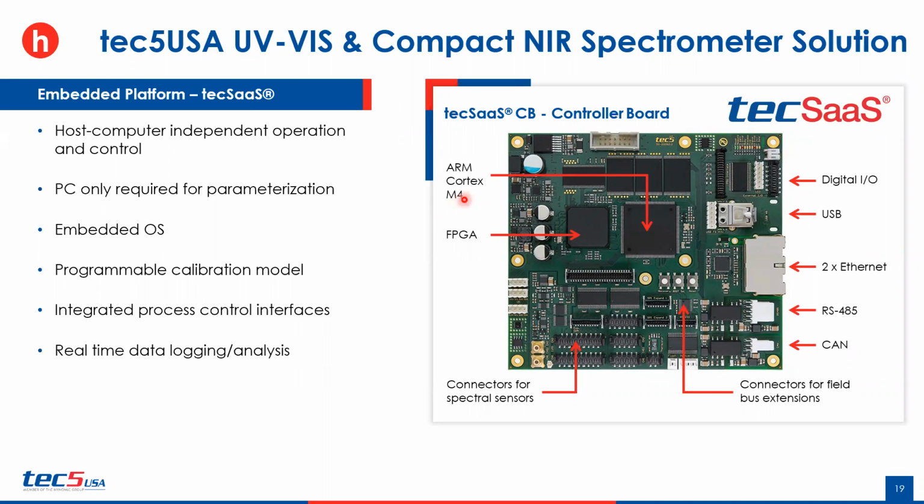So this is an additional feature of our devices that is pretty unique, and this is the embedded platform. We refer to it as our tecSaaS platform, and that SaaS is spectrometer as a sensor. This device is independent of any host computer for operation and control. So ultimately, the spectrometer is connected to a PC just to parameterize the device and load any sort of modeling or calibration to it.